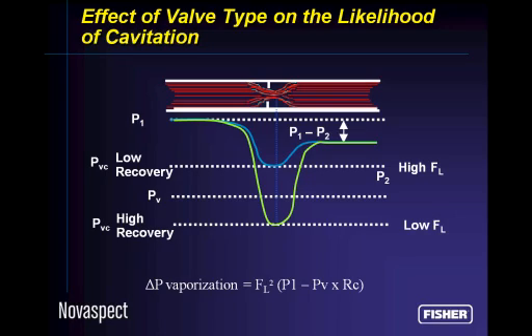We call the globe valve, it has a high F sub L, a high geometry coefficient. You remember F sub L was the term that determines the departure from the straight line ideal flow to reality, which is the fact that it heals over and we end up with some maximum flow. That delta P that causes that vaporization to occur is defined by the F sub L. We square it, we multiply it by this. P1 is the absolute inlet pressure to the valve, PV is the vapor pressure, and R sub C is the critical pressure ratio. And we know all those based on the fluid. We know the F sub L based on the valve that we pick. We can therefore calculate what differential pressure across the valve will cause vaporization and therefore cavitation or flashing. And therefore we can intelligently choose the architecture of the valve to avoid this problem altogether.